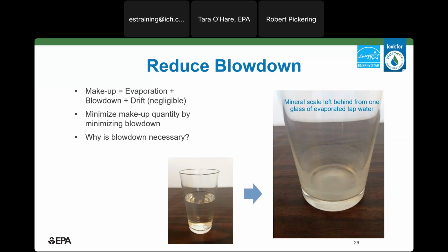The reason for this is the blowdown is to keep minerals or dissolved solids from building up in the recirculated water throughout the tower. An example of that is shown here. So city water contains dissolved solids. As water evaporates, these dissolved solids stay in circulation and begin to get concentrated over time. If the concentration gets too high, the solids will begin to form scale buildup on the surfaces of the chiller system, which can degrade performance and damage equipment.